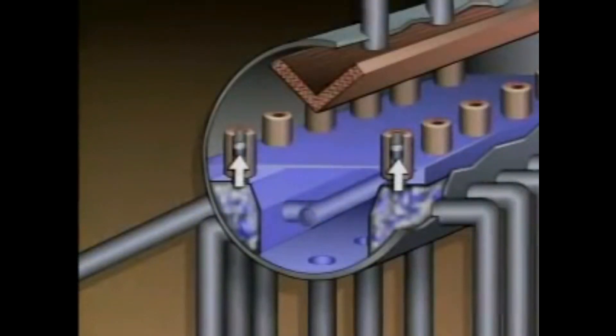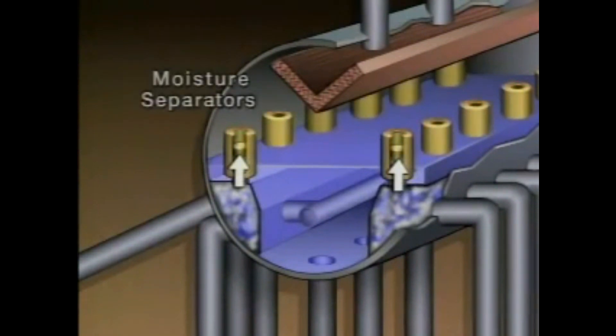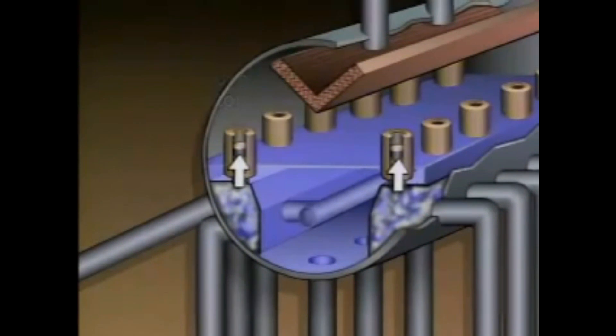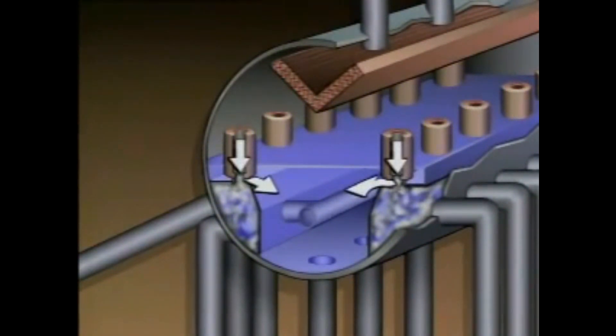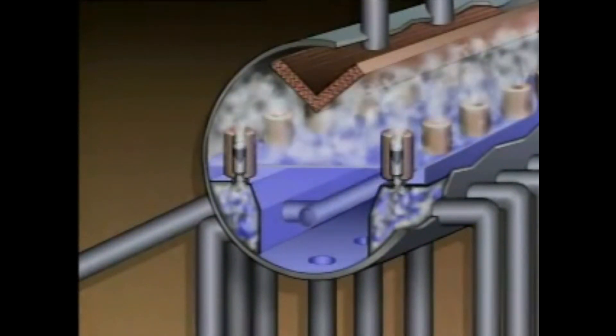The shrouds direct the mixture of water and steam into moisture separators, which are located at the top of the shrouds. The moisture separators separate the water from the steam. The water falls into the lower part of the drum, where it mixes with the feed water.